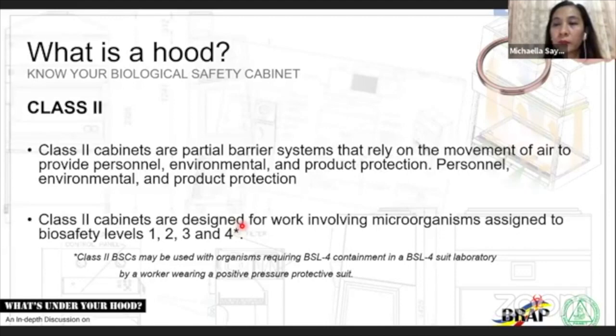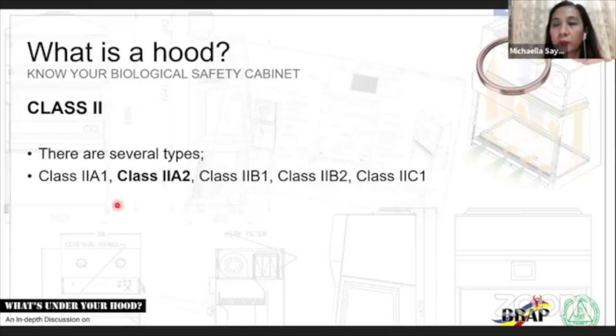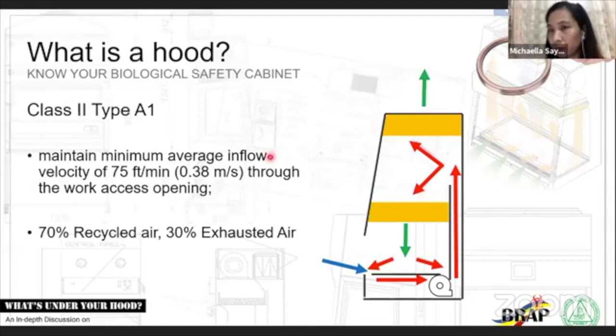Now, there are several types of your class 2. So you have your class 2A1, class 2A2, class 2B1, B2, and a newer addition, the class 2C1. Okay, for basically your class 2A1, you have your blower underneath the basin. So not directly underneath. There are dividers there to prevent your spillage from getting to the blower itself. But basically, this is how it looks. So your room air goes in. The blower creates such a vacuum that your room air comes in the front grill. That's why it's very important not to block that front grill. If you block this front grill, imagine where your dirty air will go: to your product. Cross-contamination. So work practices are important. So do not block your front grill.